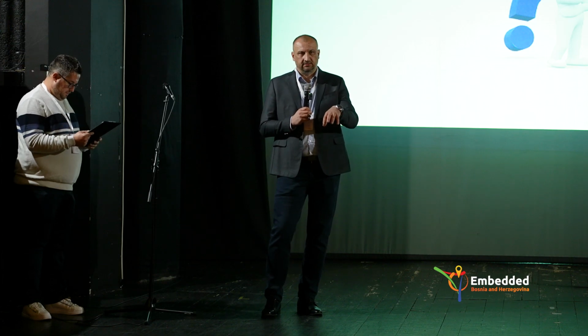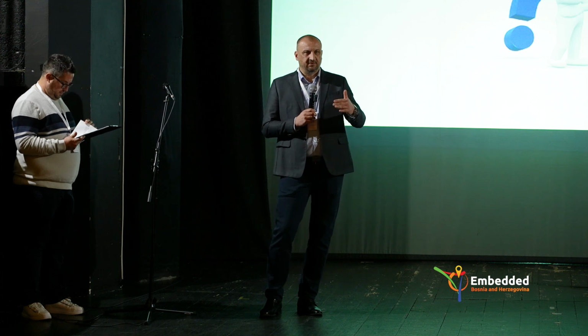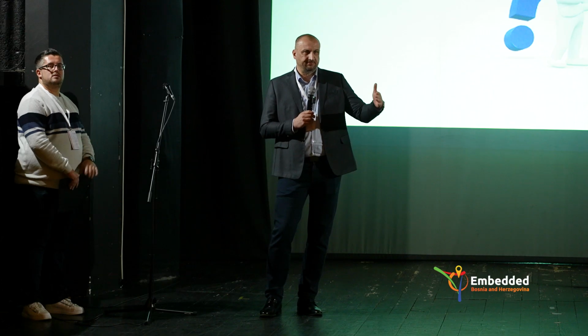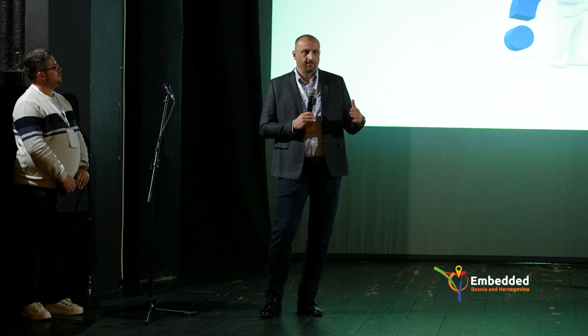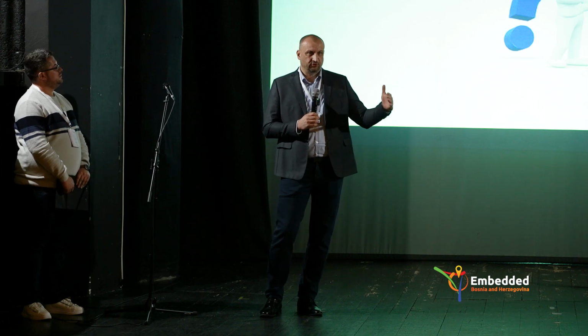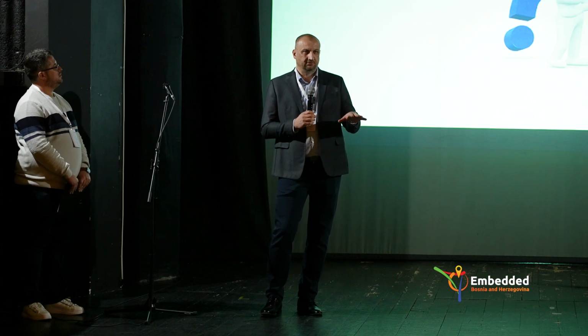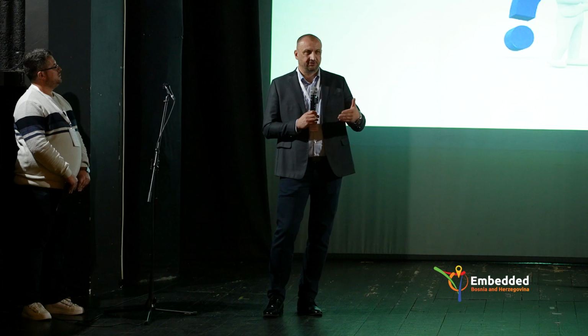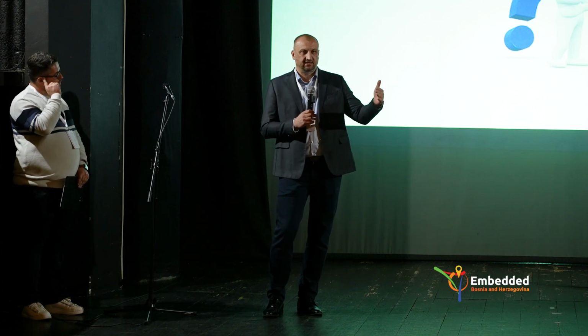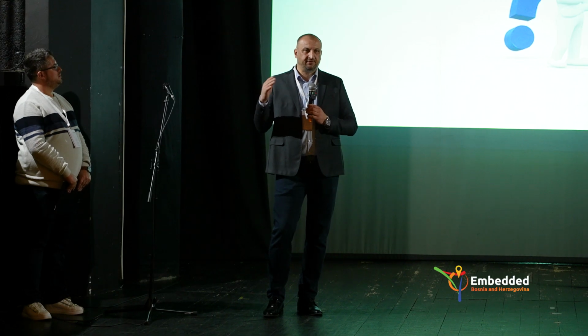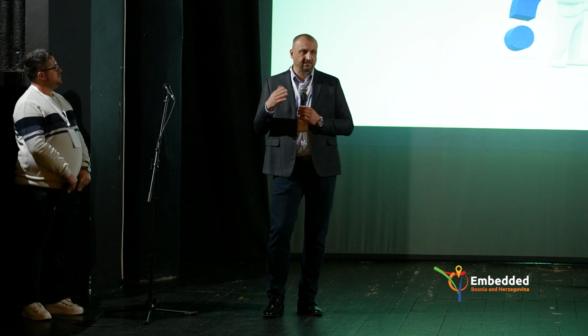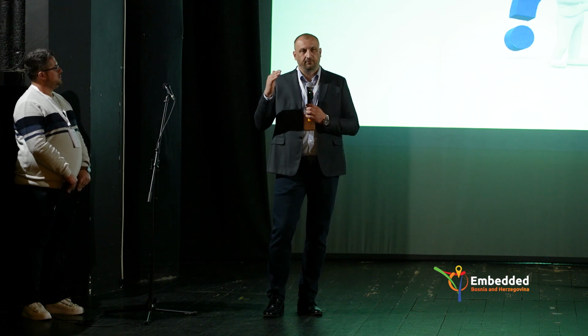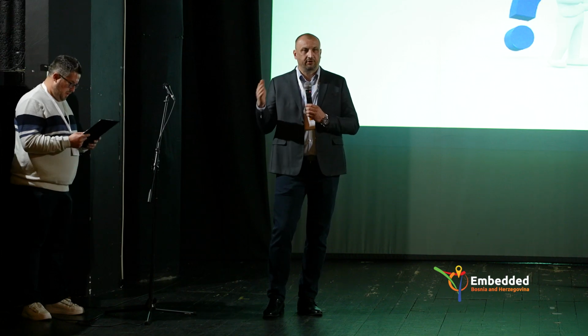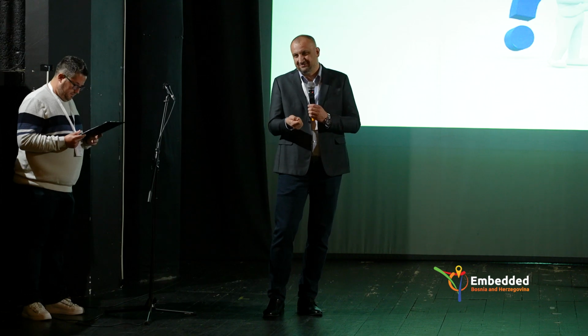Yeah. I mean, in the first place, with your design and with the components that you have planned, designed and included, your first objective is to pass the standard requirements, meaning the acceptance criteria, in an independent lab. So if you cannot pass that test, your design is not sustainable. So you have to go back and make sure that your components and everything that you have included will pass that test. But if you're declaring stricter conditions than the test is giving, that's something else. Regarding the regulatory, you have to comply with the tests, but also you have to comply with what you have promised. Otherwise, that's also not okay.